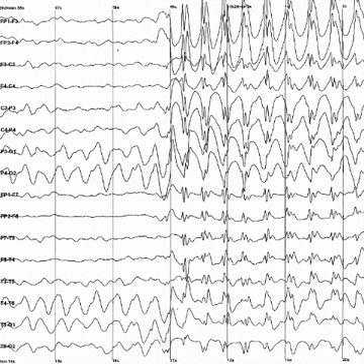In addition to artifacts generated by the body, many artifacts originate from outside the body. Movement by the patient or even just settling of the electrodes may cause electrode pops, spikes originating from a momentary change in the impedance of a given electrode. Poor grounding of the EEG electrodes can cause significant 50 or 60 Hz artifact, depending on the local power system's frequency. A third source of possible interference can be the presence of an IV drip. Such devices can cause rhythmic, fast, low-voltage bursts which may be confused for spikes.